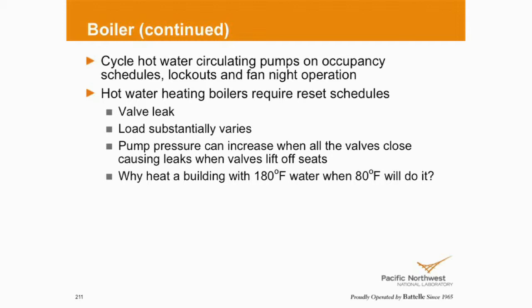So if we have that ability, can we keep the boilers hot but shut off the circulating pumps? Let the building cool down instead of baking the building at night. Again, you might have a limitation once you get to a certain temperature outside. You may have to activate your pumps, which we would understand. But if I'm just running them year-round without any regard to what the temperature is outside or the fact that I'm in a night setback condition, if I've got perimeter radiation and I'm running hot water loops because I've got to do reheat in the VAV boxes, can I go around and valve out my perimeter loops? Do I go around and valve them out?